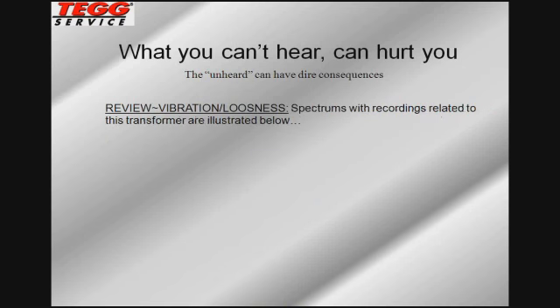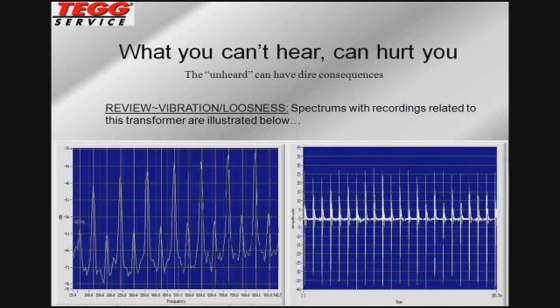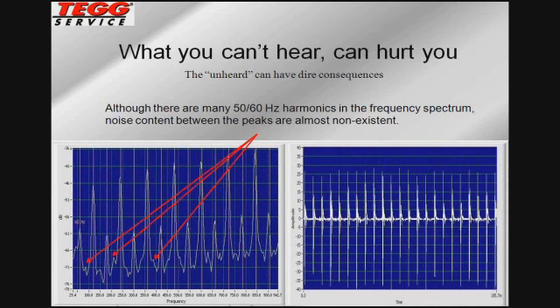If we look at a typical spectrum here with a transformer, we can see it looks very similar to corona in the frequency domain. What I mean by that is we have each 60 hertz harmonic here. However, what is missing that was in the corona spectrum is the noise content, or frequency noise, in between these peaks, which is nearly non-existent. That's an indicator that we're not dealing with corona. If you look at the time domain on the right-hand side, you can see very uniform broadband white noise, the excursions, the spacing, and the amplitude. That's very typical of a properly functioning transformer.